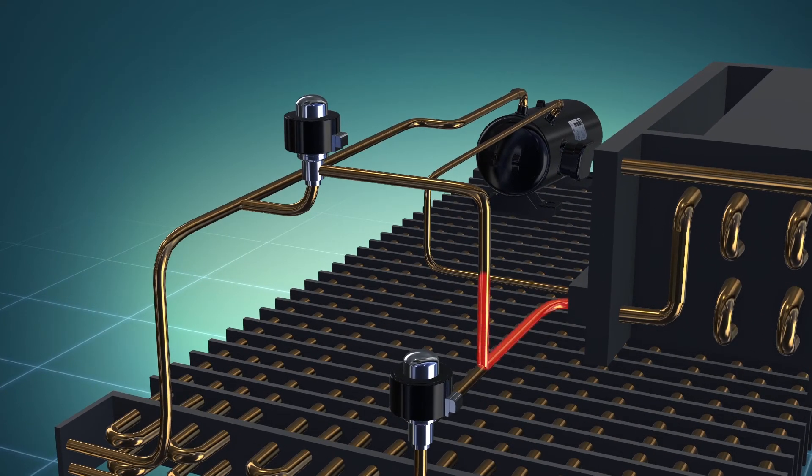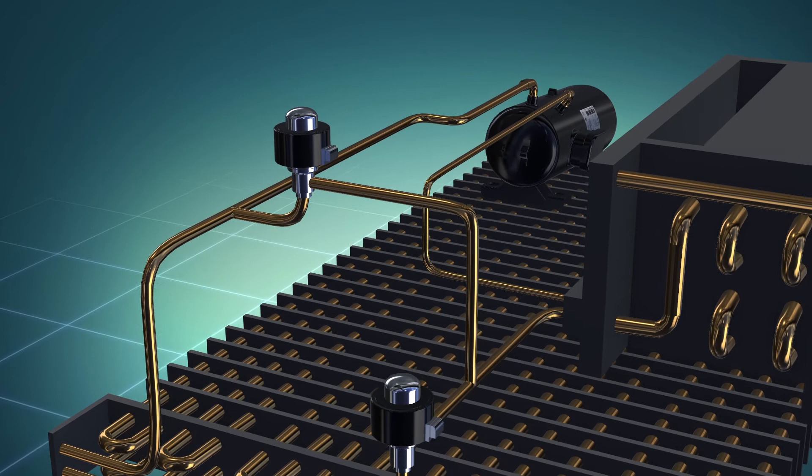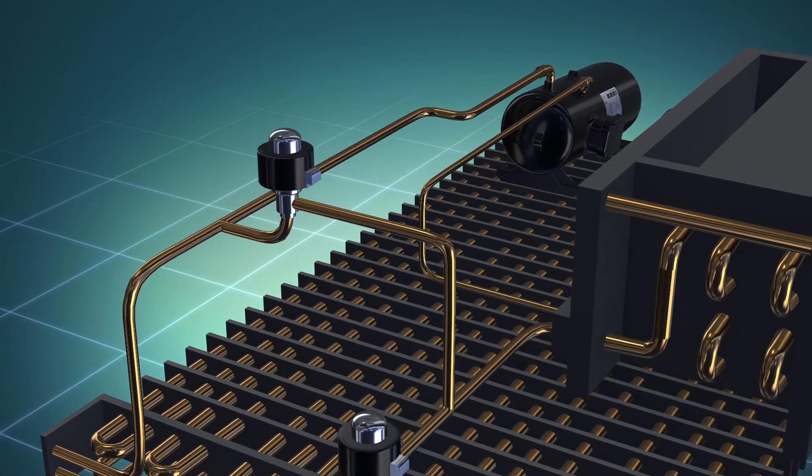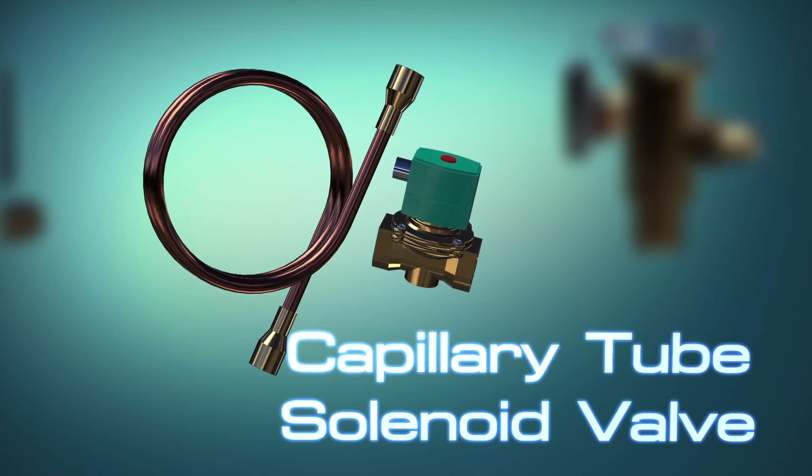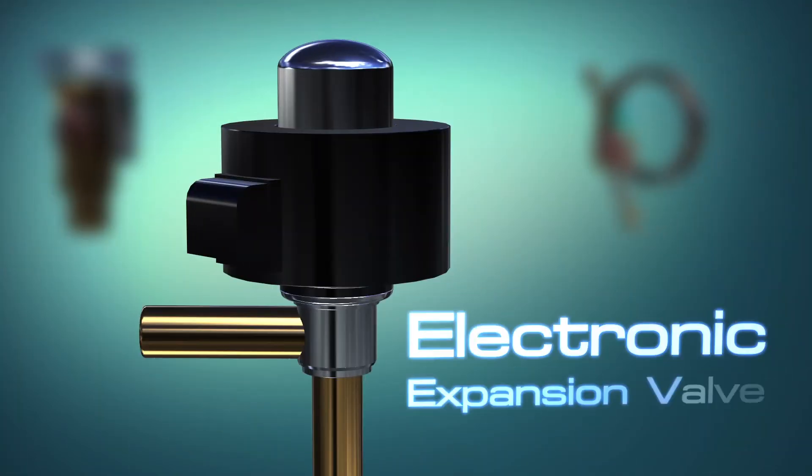The additional device connects from the condenser to expansion device and then to the compressor's suction pipe. There are three ways to connect the expansion device: by using solenoid valve and capillary tube, thermostatic expansion valve, or electronic expansion valve.